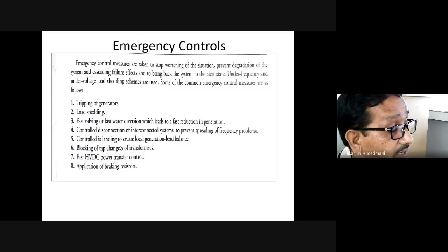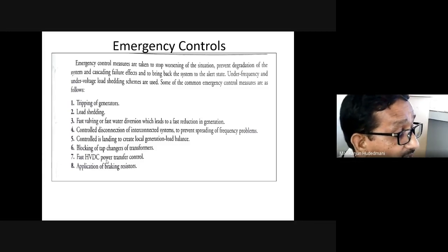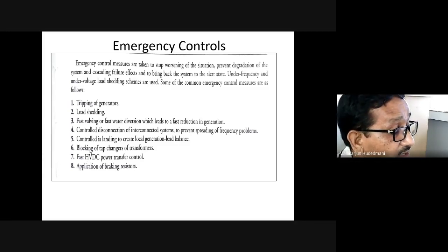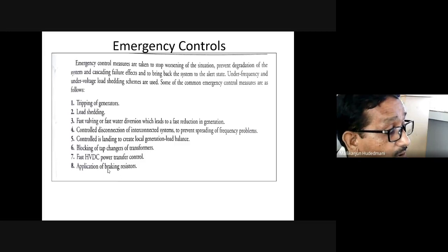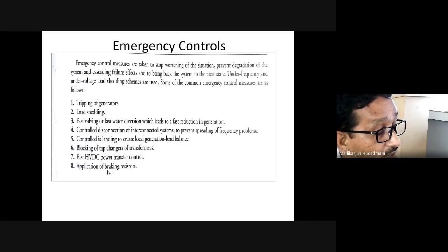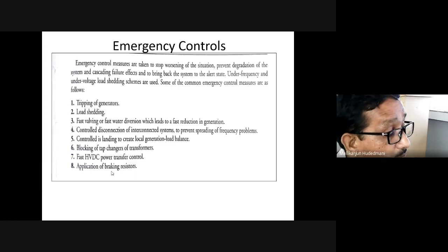Blocking of tap changer. Don't allow the tap changer to simply shift and try to boost the voltage. Otherwise, transformers get lost. So block the tap changer so that such a mechanism prevents the emergency. And fast HVDC power transfer control. Make the HVDC transfer controlled appropriately so that such an adverse phenomenon is brought under control.